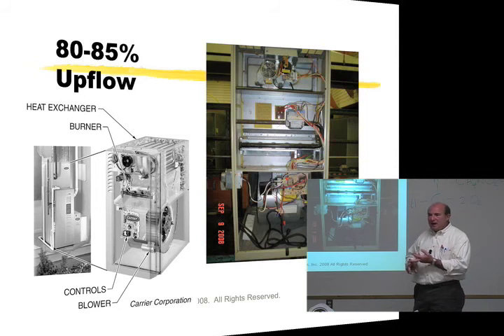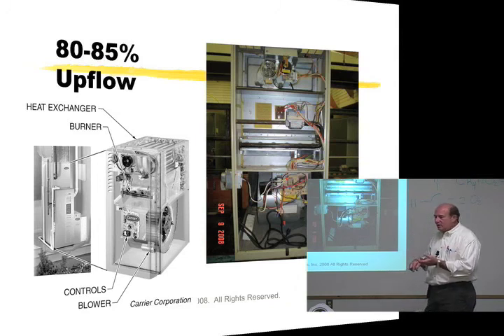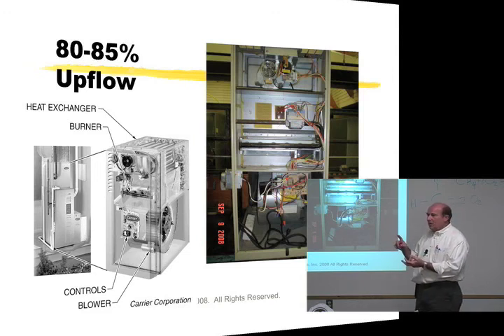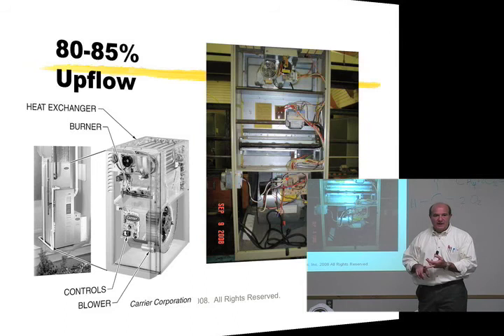And depending upon which winding in that blower motor, you can select what those speeds might be. Now here in Denver, I almost always put everything on high speed because we're at altitude here, we have thinner air, and it takes a little bit more to get heat and cooling into a space. But you can select maybe high speed for cooling and medium low speed for heating. You don't need nearly as much air for heating as you do for cooling.